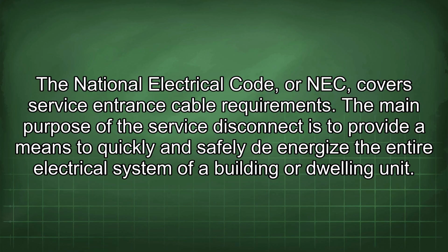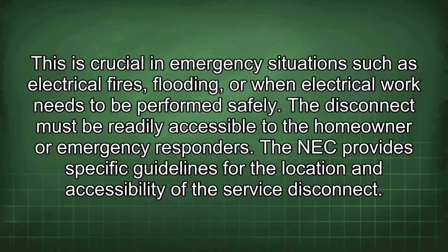The main purpose of the service disconnect is to provide a means to quickly and safely de-energize the entire electrical system of a building or dwelling unit. This is crucial in emergency situations such as electrical fires, flooding, or when electrical work needs to be performed safely. The disconnect must be readily accessible to the homeowner or emergency responders. The NEC provides specific guidelines for the location and accessibility of the service disconnect.